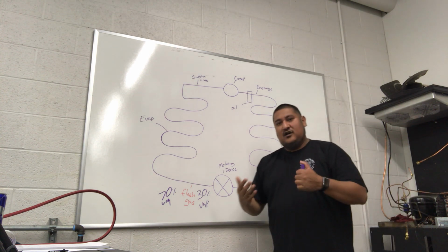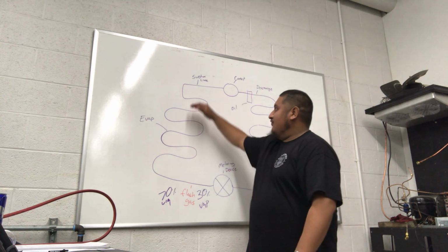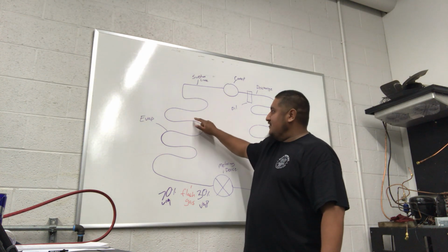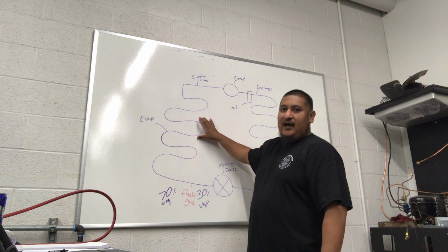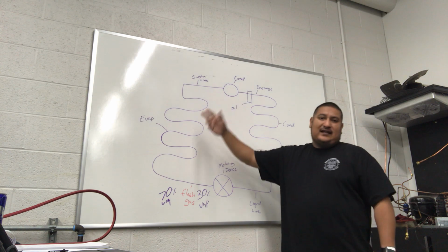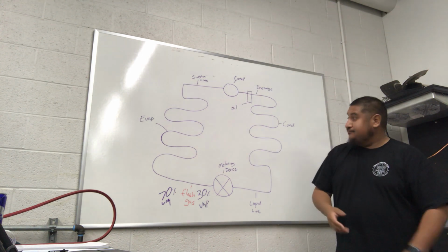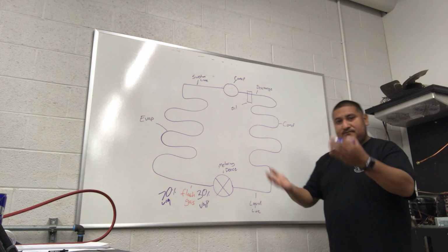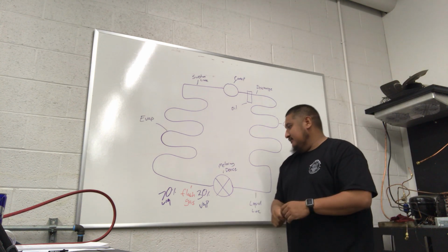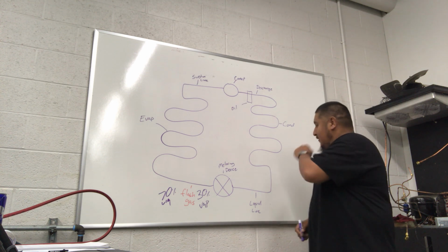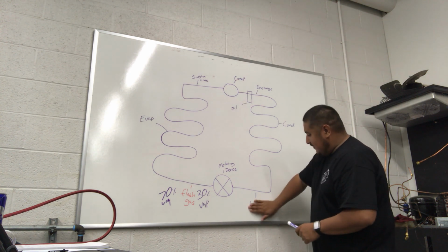Then we have something that's called oil logging. So you can have your entire evaporator coil here kind of frosted up, and you'll see a nice little spot where it's still thawed out. Or more than likely, you're going to have a little bit of oil just hanging out there, and that can actually hurt the efficiency of your unit. It can cause a restriction inside your evaporator. And then your pressures get all goofy, and sometimes a new unit is required.